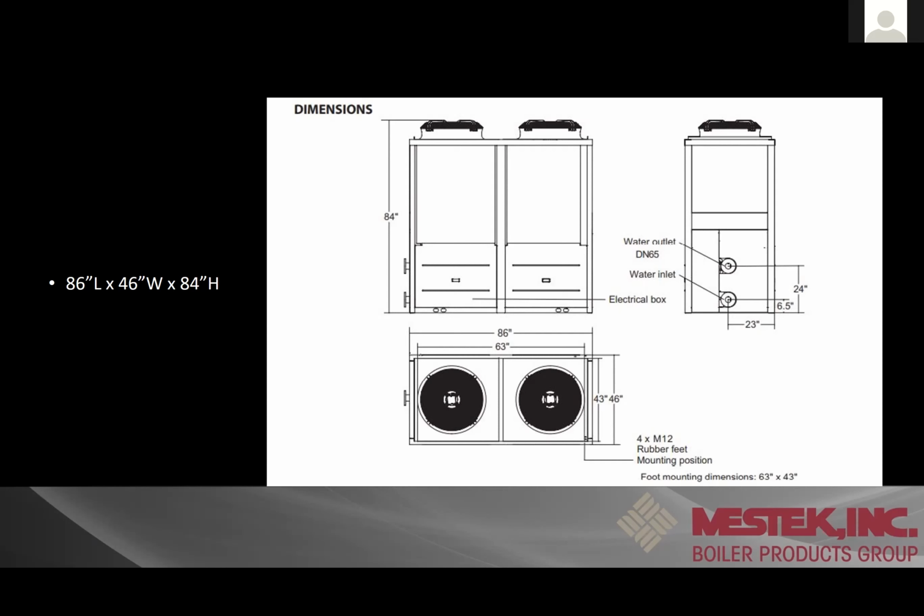All right. Just so everybody knows, this product is a single wall heat exchanger on the shell and tube side. So it cannot have domestic water going directly through it. That being said, you could add a secondary plate heat exchanger on the water side and do domestic that way, or some type of indirect water heater. I've also seen some people using electric water heaters, so they have electric backup and then they're feeding it through that as well. Currently, this is really more of a heating cooling unit, not really doing domestic water unless you're going to add some extra heat exchangers to be able to do that.